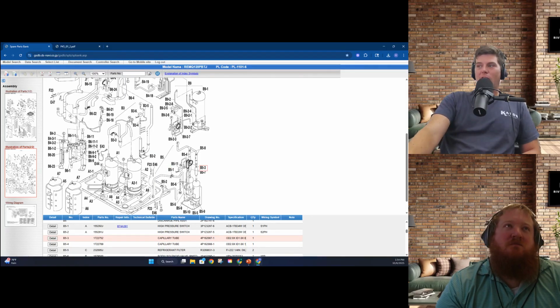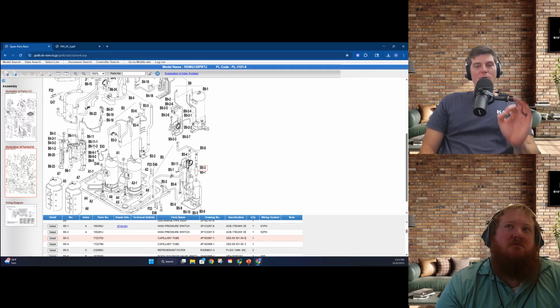And so where does the vibration go? Well, it goes up through the cap tubes over to the oil refrigerant separator line, and it just causes them to either rub out, or it gets that perfect spot of heat, pressure, vibration, micro cracks, and then what happens when you have 400 psig of head pressure on a line like that? It ruptures, right? It breaks, blows apart. So what causes it? Bearing failure in compressors.